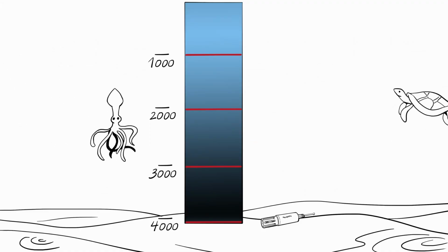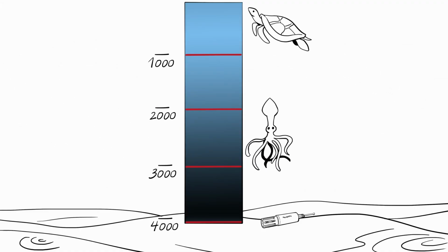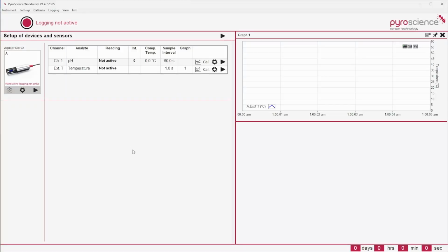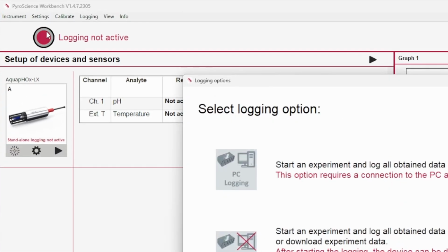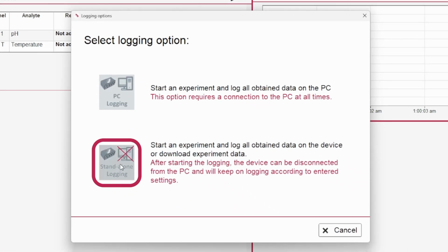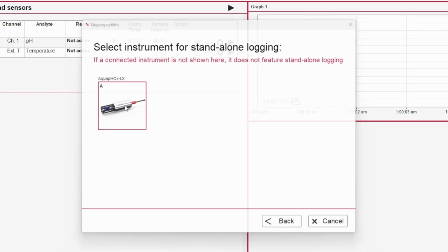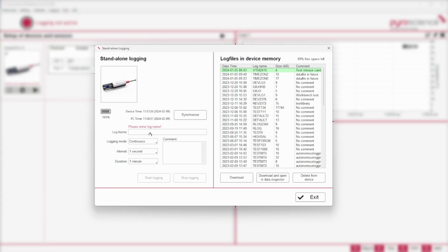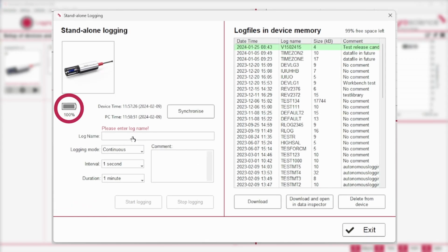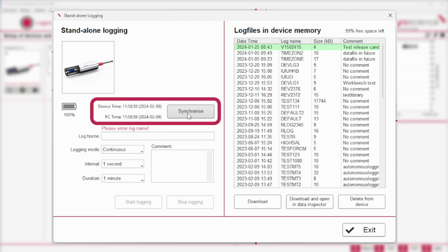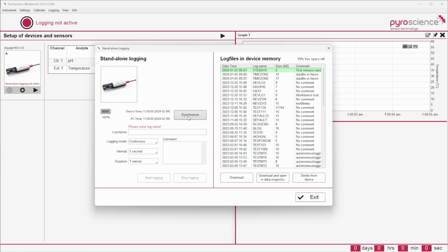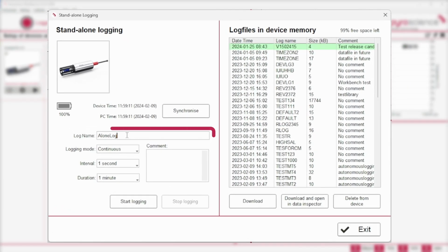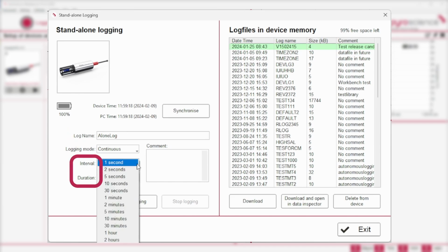The AquapHOx Underwater Logger offers the option to log the data without a PC connection. After the configuration and calibration, click on the red button below the menu bar and select the standalone logging option in the connected AquapHOx Logger. In the new window, you will find on the left side the battery level. The battery is charged during direct PC connection. Ensure that your device is synchronized to the PC time. This is especially important if other third-party sensors are used simultaneously. Enter a unique log name with 1 to 8 characters and select the duration time.